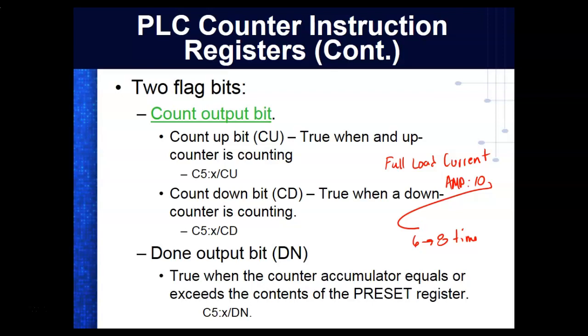It's a letter, like A, B, C, D, and then you look it up on a chart and it tells you the multiplier. That's a really good question. I need to know that, but it doesn't come to my mind right now. So technically, this motor right here can pull 60 to 80 amps when I try to start it, just to get it started.